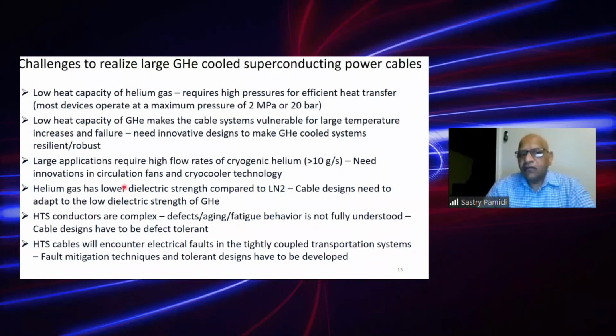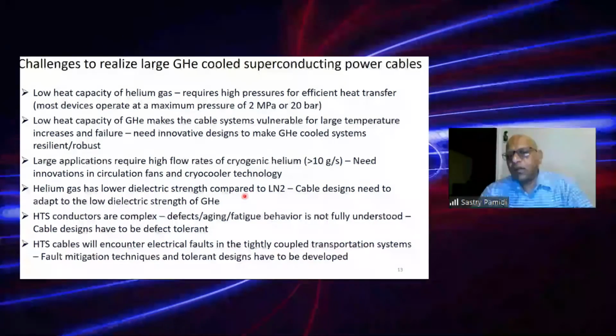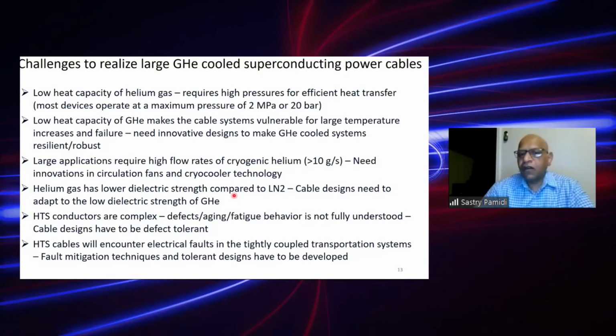And the second challenge, which is important, is that even if you go to 2 megapascal, that is 20 bar, helium gas has low dielectric strength. That means its use as electrical insulation is not suitable for power devices. We have to have a very good electrical insulation system design, and that has been one of our focuses for the last several years, because we have shown that we can use helium gas for cooling power devices. We started focusing on the dielectric strength aspect of helium gas.